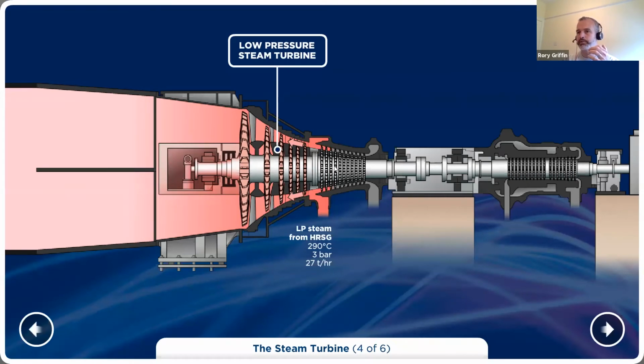And that's a bit of a nightmare scenario, because that means the blades could actually touch the shell casing here. There's very fine margins because you don't want your steam escaping around the blades. You want to catch as much of it as possible. So there's very fine clearances between the blades and the shell casing. So when the unit comes off, it goes onto turning gear, and it'll sit there for about three to 3.5 days until it's cool enough to take it off turning gear. So that's the steam turbine.